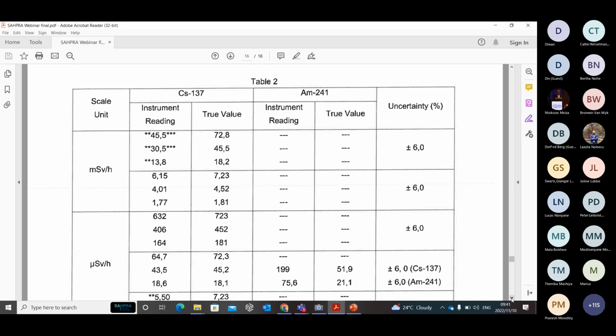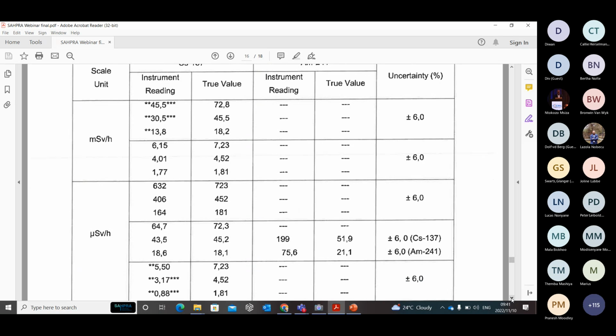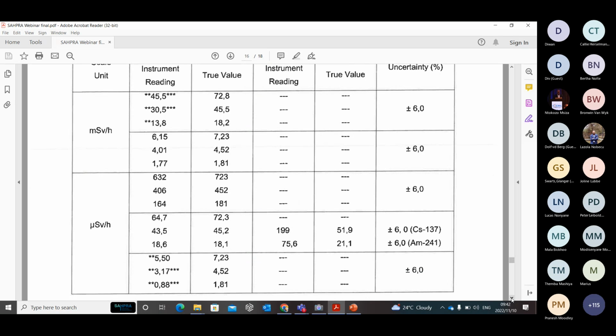With the uncertainty, as we go down, you will see a certain term that we use, confidence level. That means that we are 95% confident that your instrument reads this value to this uncertainty. And for that, we assign a factor of 2, which goes with the level of confidence.